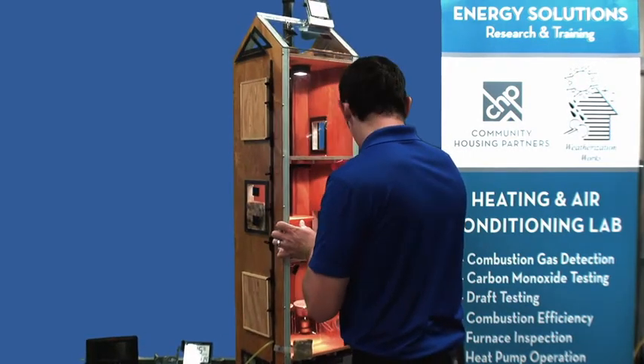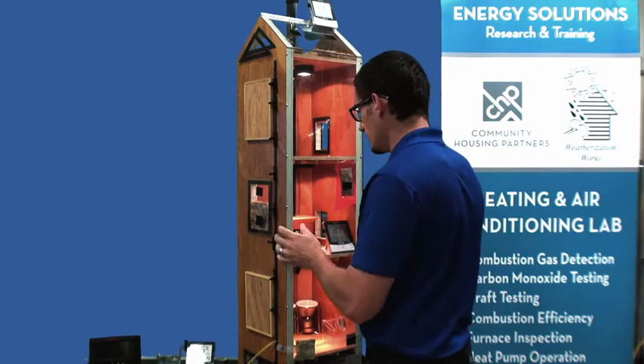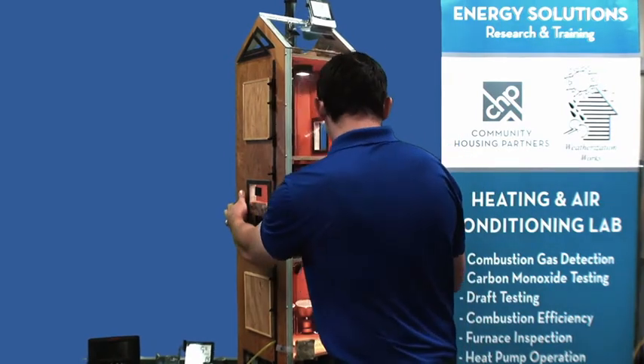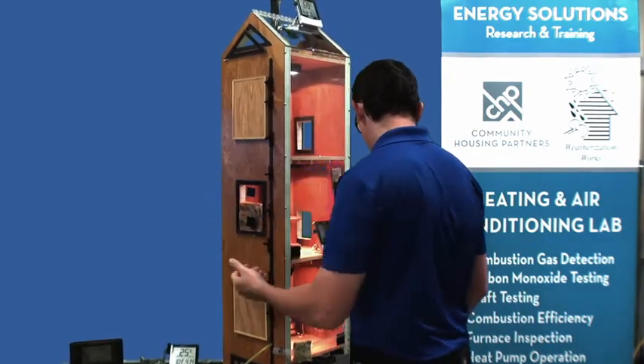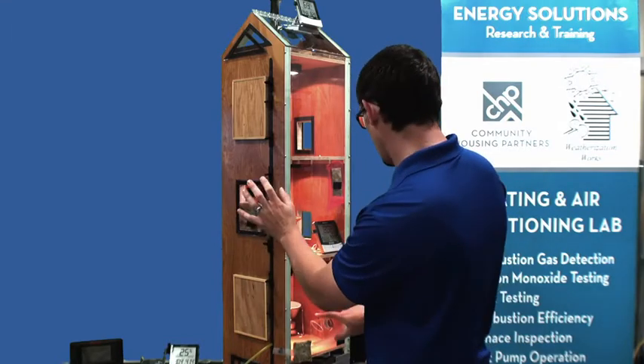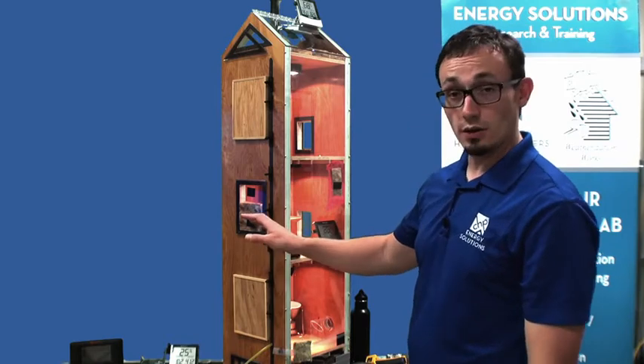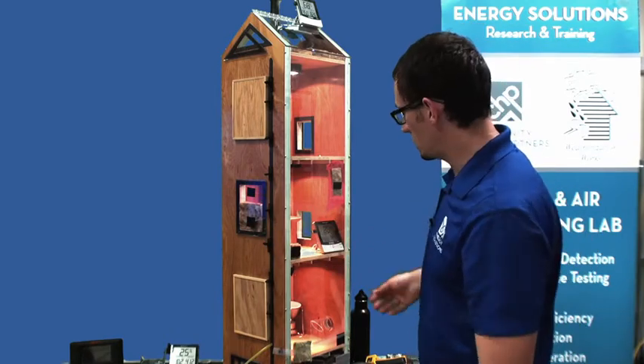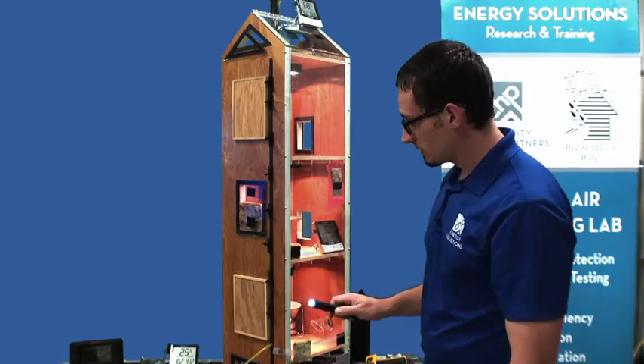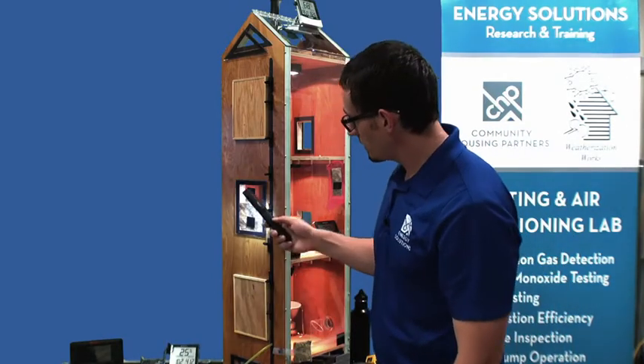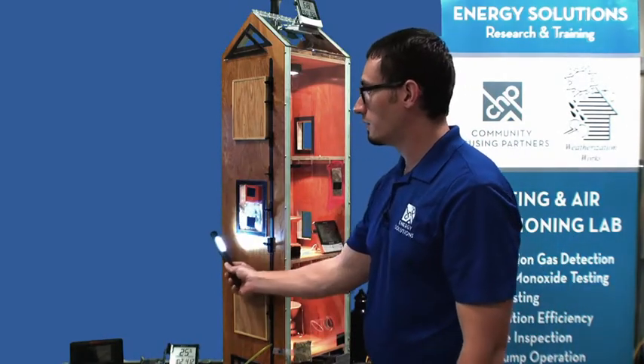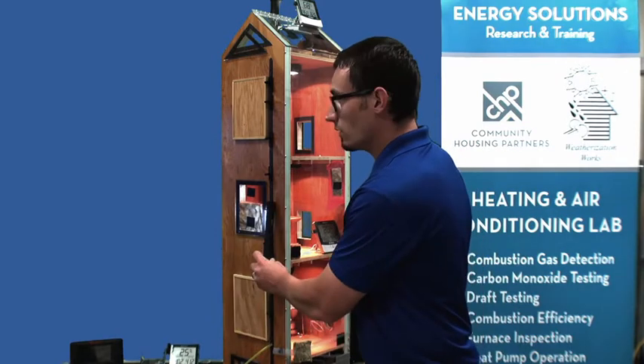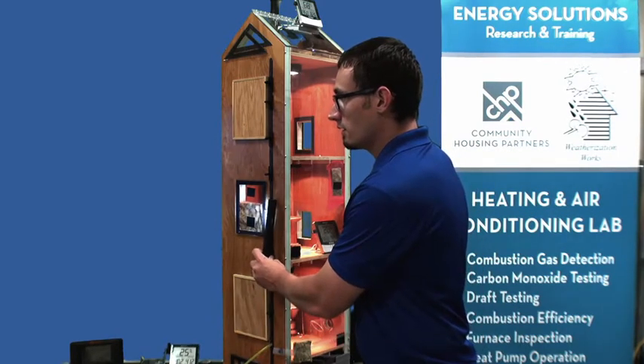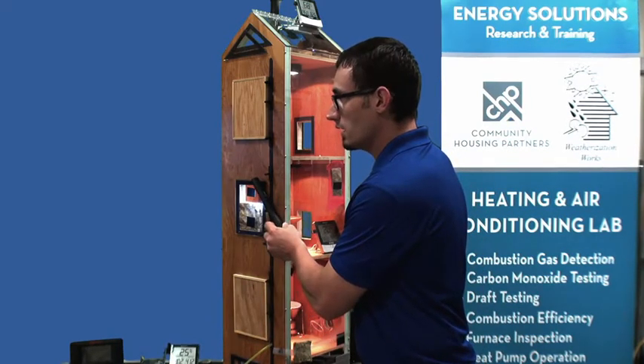Maybe expect a little quicker condensation over here as well, because of that insulated pocket and the distance away from the heat source, this actually ended up being the location with the lowest surface temperatures in the whole building. So, take a look. Ooh, yeah. Let's find the angle that works good for that. You guys can see that condensation on there.